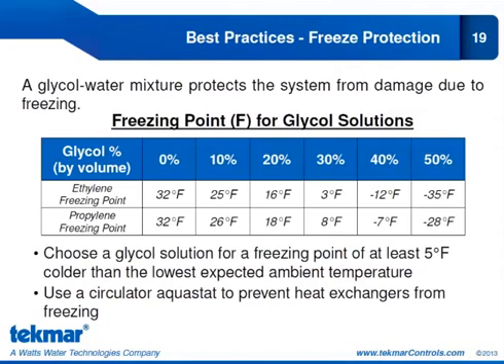Another best practice is freeze protection. Snow melt systems typically operate at very low temperatures, so a glycol-water mixture is essential to prevent damage from freezing. There are two types: ethylene and propylene. Propylene is the standard recommendation because it is non-toxic, unlike ethylene. Choose a solution that gives a freezing point at least 5 degrees colder than the lowest expected ambient temperature — typically around 40% propylene. Using a circulator aquastat is also recommended to prevent heat exchangers from freezing, which will be covered in the 654 control applications.